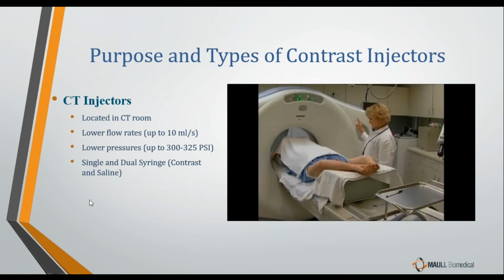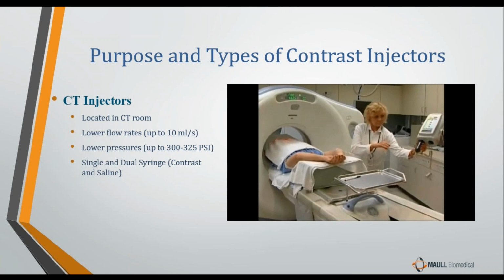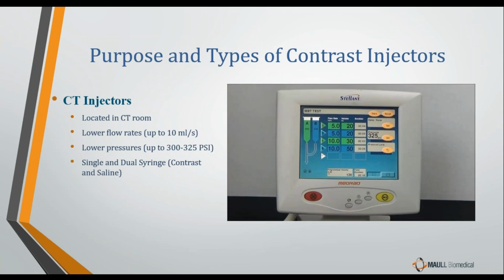Now, the other kind of contrast injector is a CT injector. And obviously, this injector will be located in the CT room. Now, unlike its angiographic counterpart, the highest flow rate that a CT injector can be programmed to is 10 milliliters per second. And again, that's also due to the nature of how a CT procedure is done. CT procedures are relatively slower procedures, so there's never a time when we need a massive quantity of contrast injected very rapidly. So at its highest end, a CT injector can only inject contrast fluids or saline fluids at a rate of 10 milliliters per second, which compared to the angiographic injector we just talked about is very, very low.